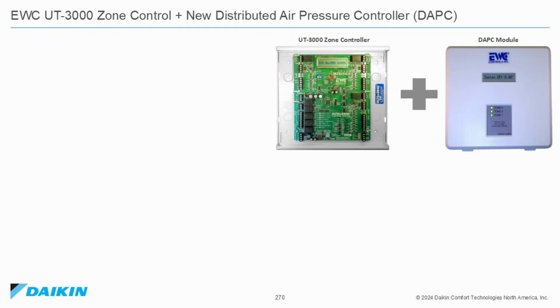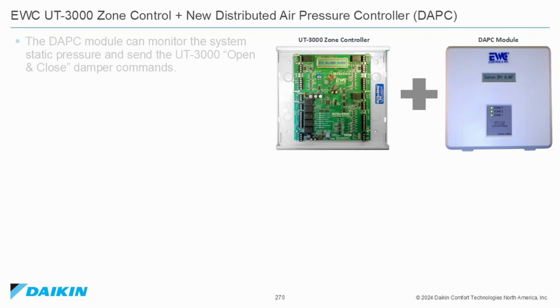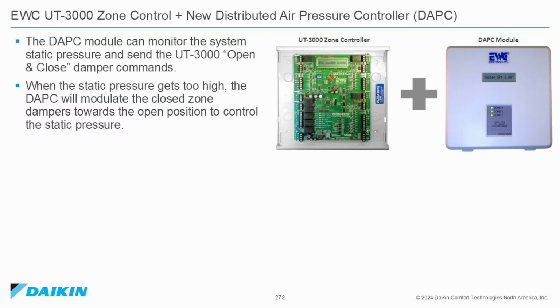The EWC UT3000 Zone Control plus the new Distributed Air Pressure Controller, DAPC. The DAPC module can monitor the system static pressure and send the UT3000 open and close damper commands. When the static pressure gets too high, the DAPC will modulate the closed zone dampers toward the open position to control static pressure.